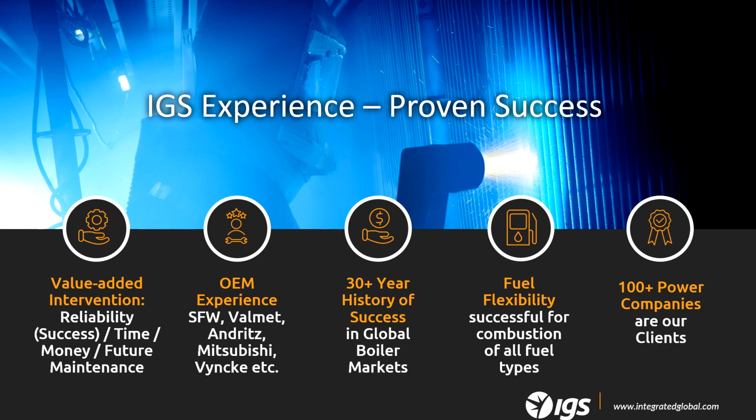But also we worked in greenfield sites as well, where high velocity thermal spray has been used as an alternative to, for example, the more traditional 625 weld overlay to protect the tubes from new in that boiler. We do applications onto the black carbon, but also we apply on top of the 625 weld overlay to extend the life of the panels with an overlay already installed. And that's to prevent, again, panel replacement in boilers, particularly in units where there's a high requirement for uptime. So looking for that high 90s in terms of availability of the asset.